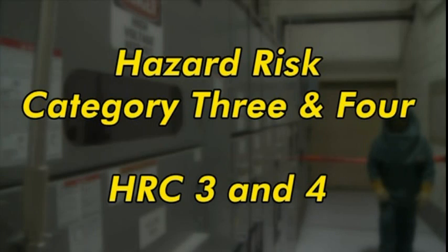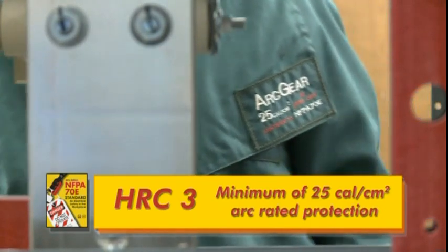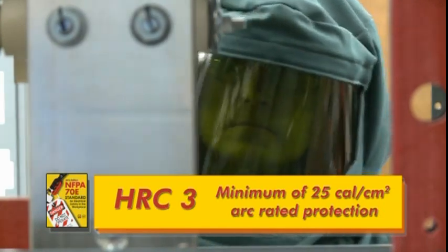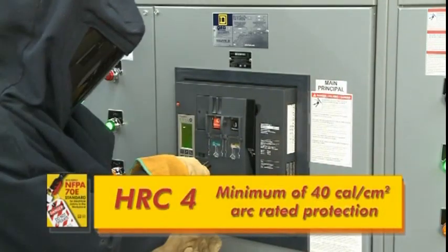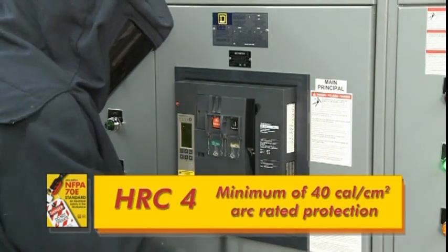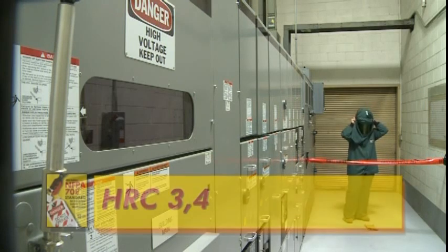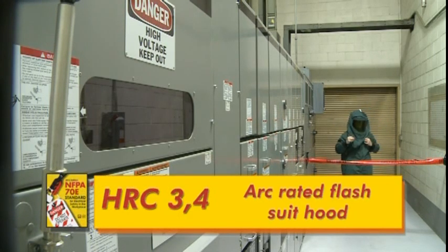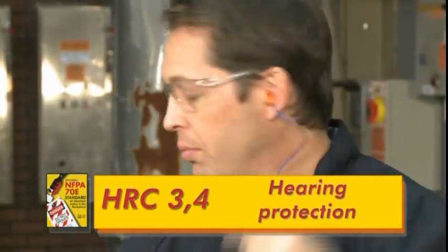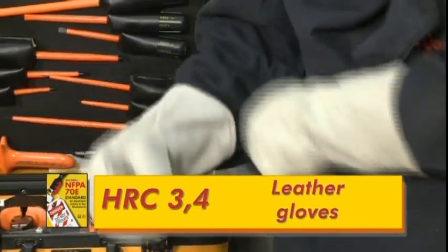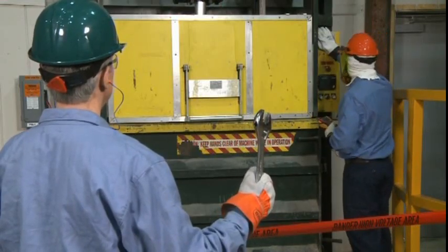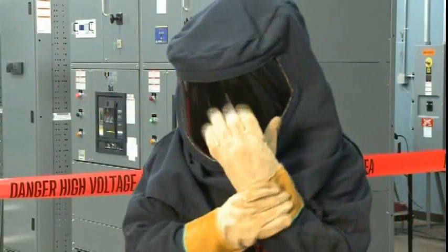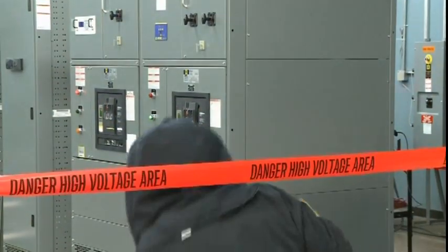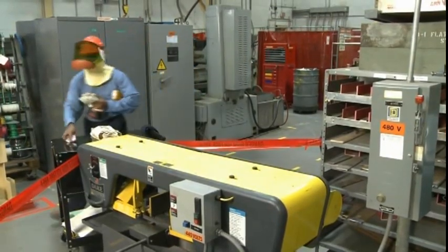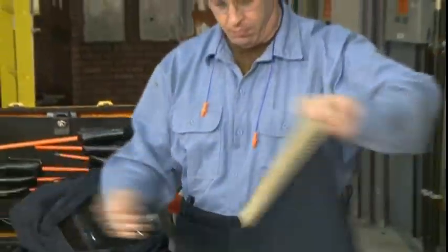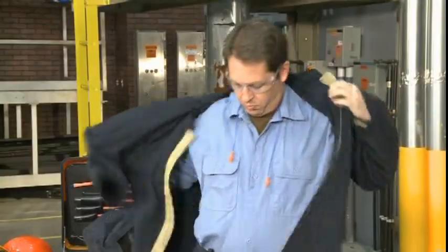Hazard risk category 3 and 4. Hazard risk category 3 requires a minimum of 25 calories per centimeter squared arc-rated protection, and hazard risk category 4 requires a minimum of 40 calories per centimeter squared arc-rated protection. These categories also require an arc-rated flash suit hood, a hard hat, safety glasses, hearing protection, leather work shoes, and leather gloves. For ease of PPE selection and cost savings, many facilities only use Category 2 or Category 4 PPE. At these facilities, electrical workers dress in Category 2 as standard work practice. Then add a Category 4 flash suit and hood for any task that exceeds Category 2.